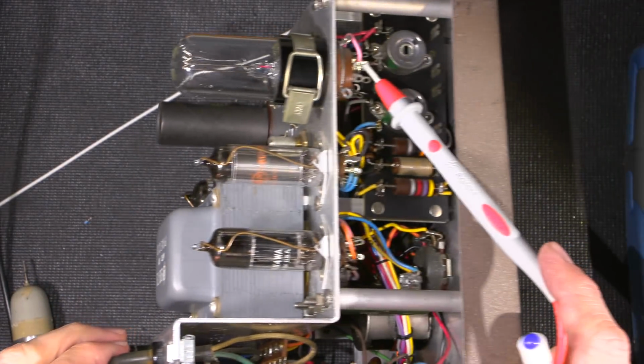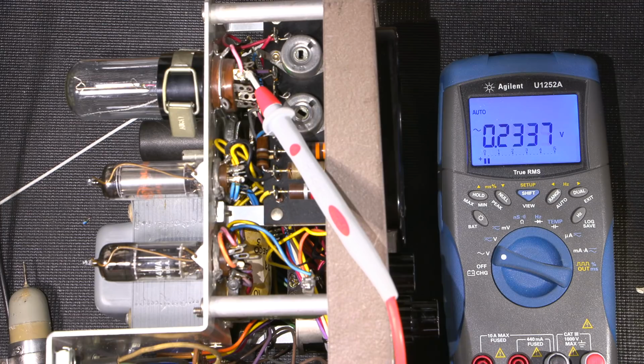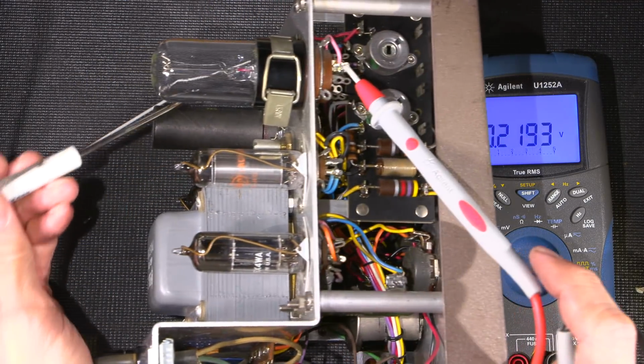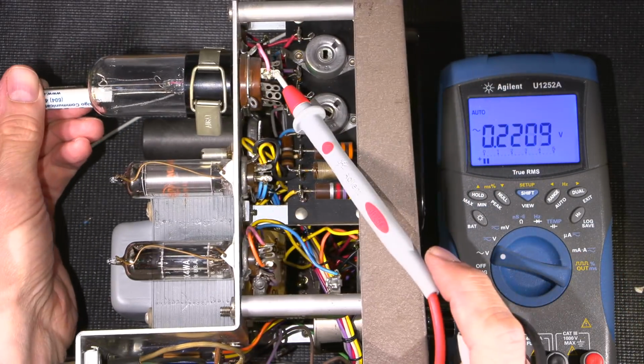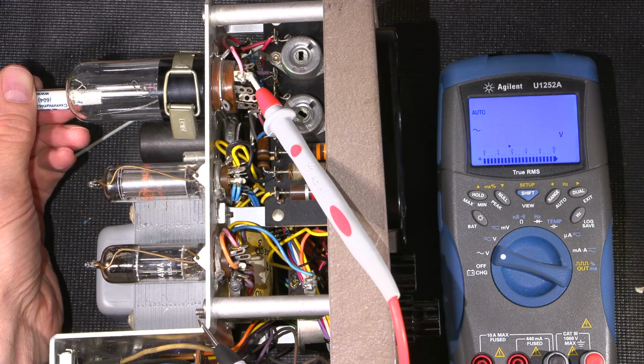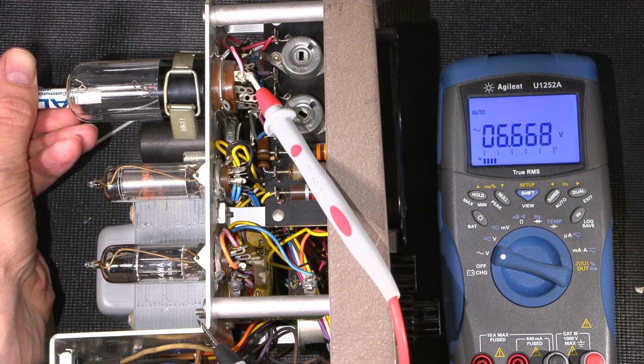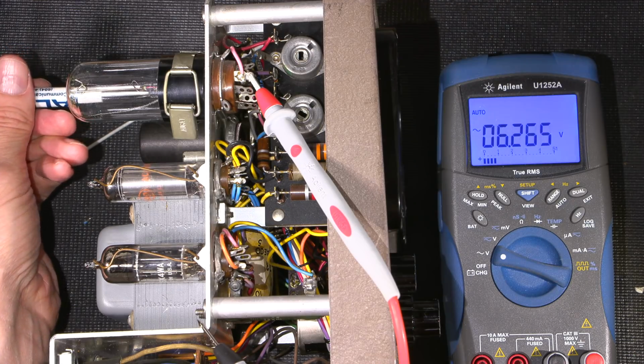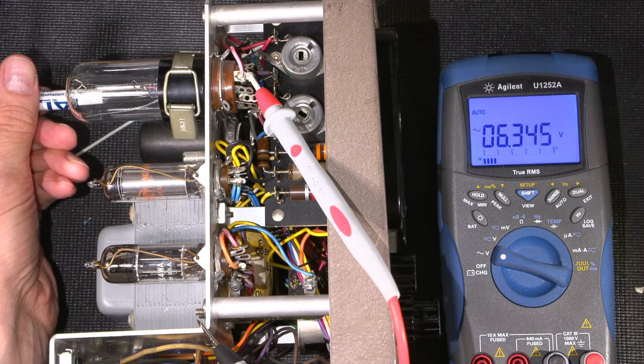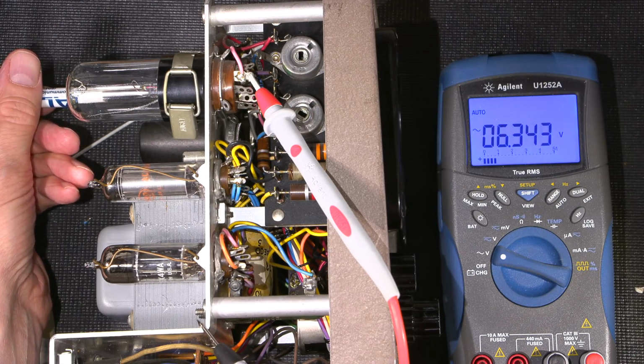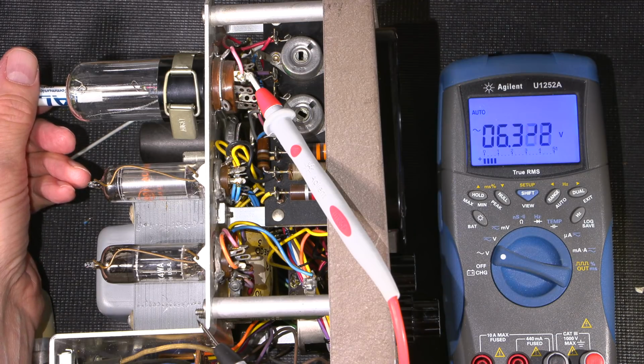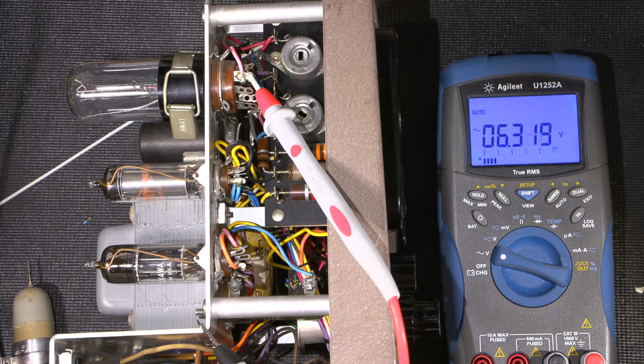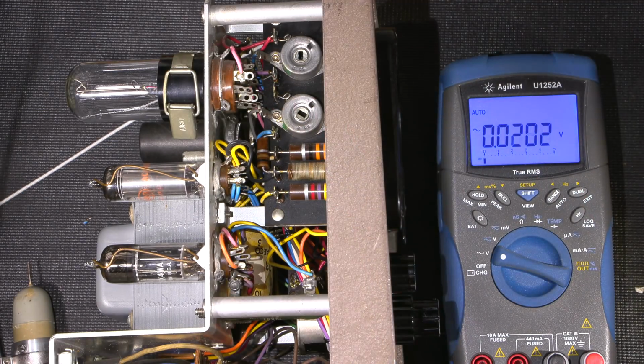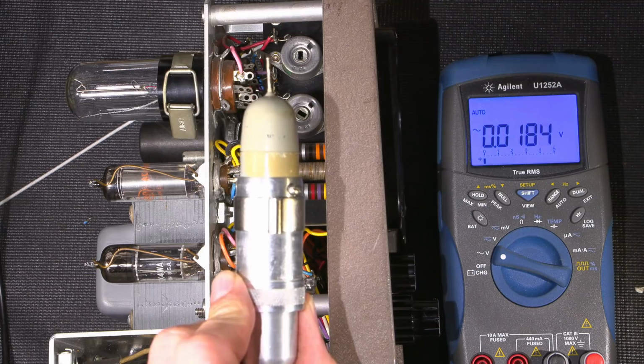This one right here. Looks like somebody's marked a line on there. It doesn't look to be too accurate. So what I'll do is put my screwdriver in that adjustment point, just like so, and I will bring this down to 6.3. I'll bring it just a touch over 6.3, just to deal with line variation. The line here is actually pretty high at the bench, so a normal line would probably be right at 6.3. So that's close enough, and that will definitely save the filament in that little tube. So, probe filament voltage adjusted.